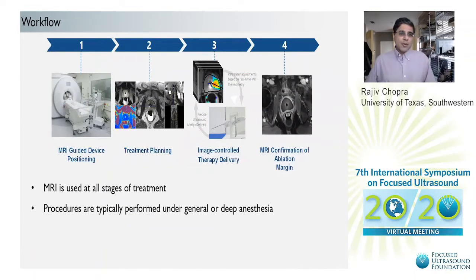The workflow is not that different from externally guided focused ultrasound as we're familiar with it, but there are some small differences. What's similar is that MRI is used at all stages of the treatment, as it is for all focused ultrasound procedures. What's different is that these are typically performed under deeper anesthesia or even general anesthesia, depending on the invasiveness of the device and where it goes. So that's typically a difference. But there's a phase of insertion of the device and MR-guided device positioning to get to the right location, treatment planning using imaging, then image-controlled therapy delivery, and it's been shown, at least in this technology, that true imaging feedback for precise, temperature-controlled therapy is feasible. And then finally, confirmation of the ablation with imaging, which is typical for most focused ultrasound procedures. So really, there are not that many differences other than maybe the deeper level of anesthesia and the invasiveness.